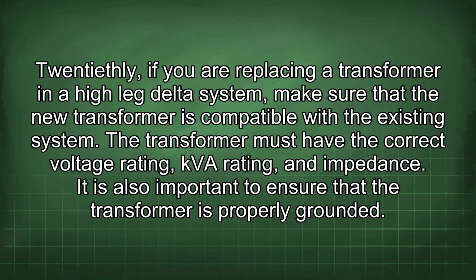20thly, if you are replacing a transformer in a high-leg delta system, make sure that the new transformer is compatible with the existing system. The transformer must have the correct voltage rating, kVA rating, and impedance. It is also important to ensure that the transformer is properly grounded.